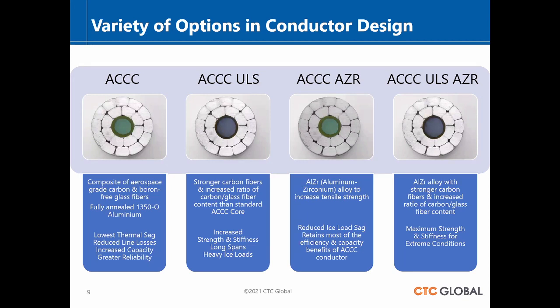On this slide, I only want to show that in addition to the base product, the ACCC, and there are 31 different sizes in the US, another 40 different sizes in the international market. So it's quite a range of sizes for the product, but then there are stronger, sturdier products beyond the base. So if you've got ice loading, particularly long spans, extra long spans, or heavy ice loading, you would move to the right. For Montana, we believe, at least what we've seen, and we'd like to work with the utilities to see if this is any different, but we think most of those will be served by this ULS, and certainly by the time you get to the third product there, most all the applications for heavy ice in Montana should be able to be served up through those three products. If you need even more and even extreme, you can move on to the last product there.